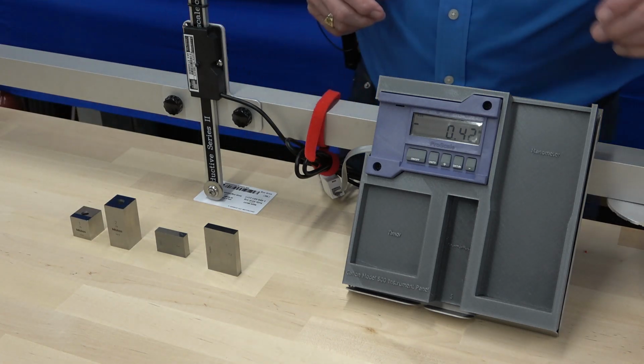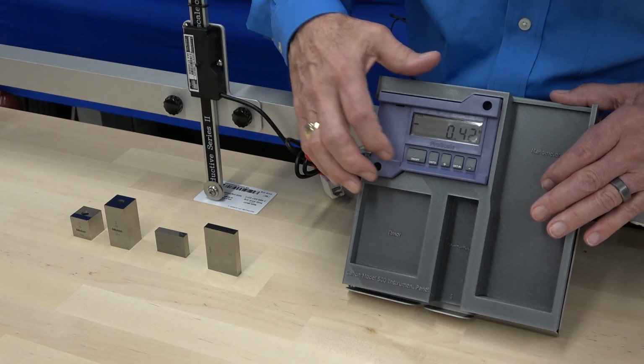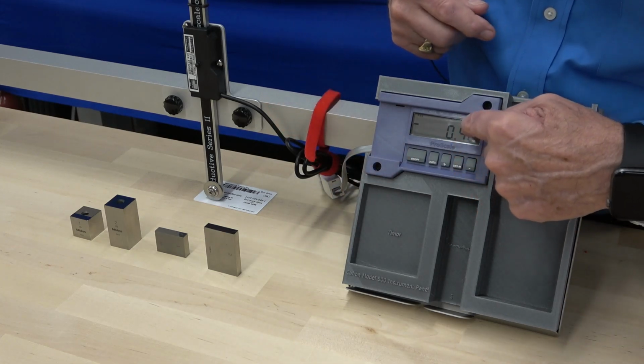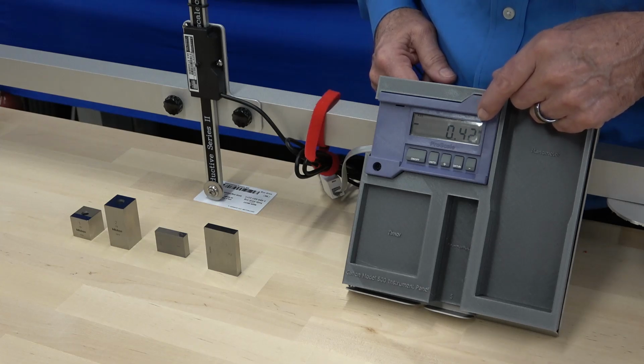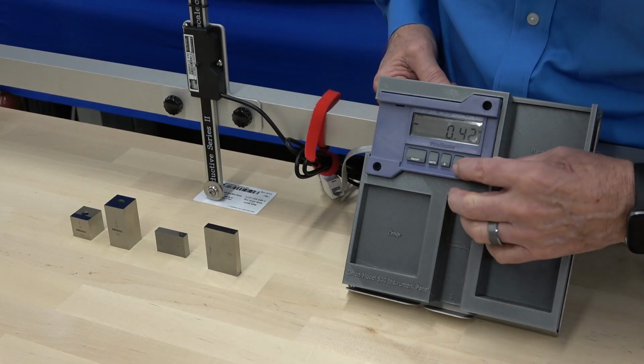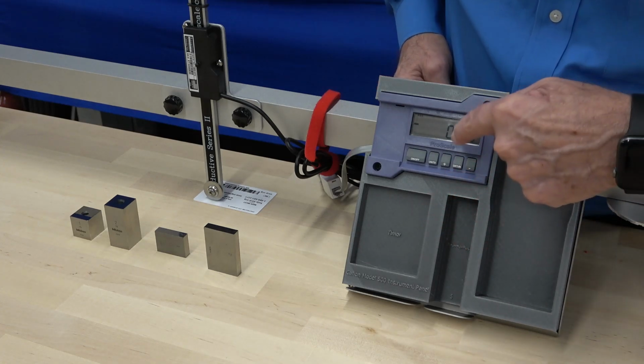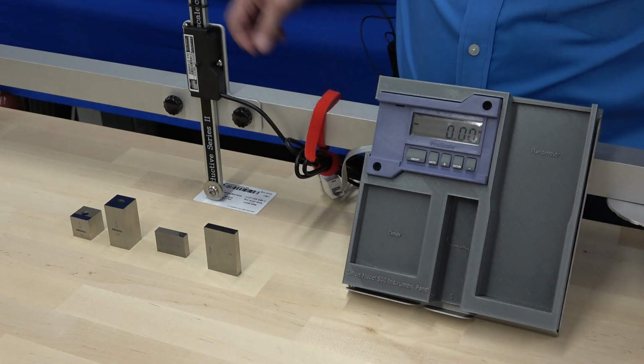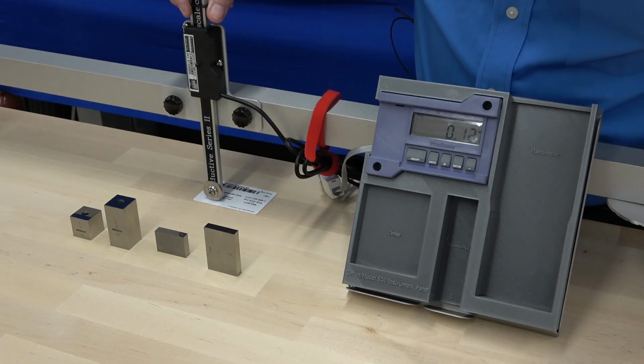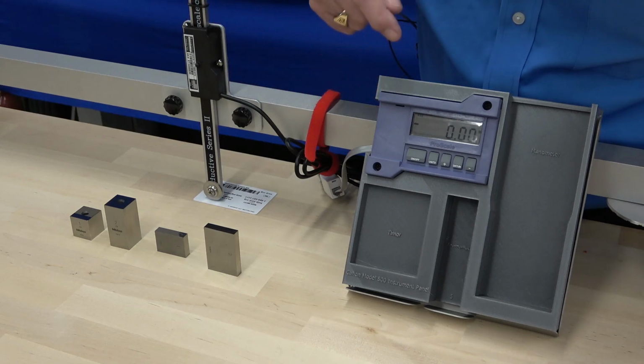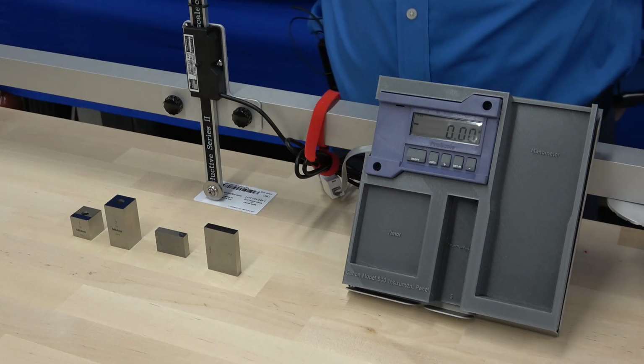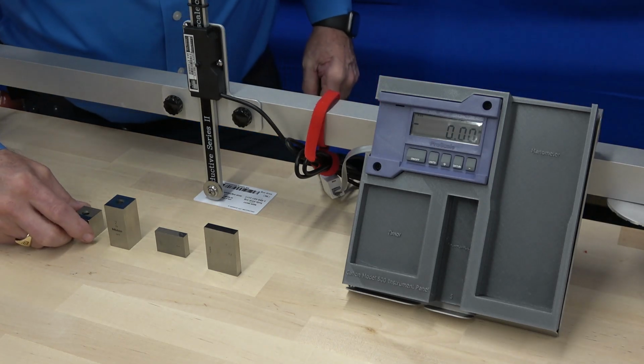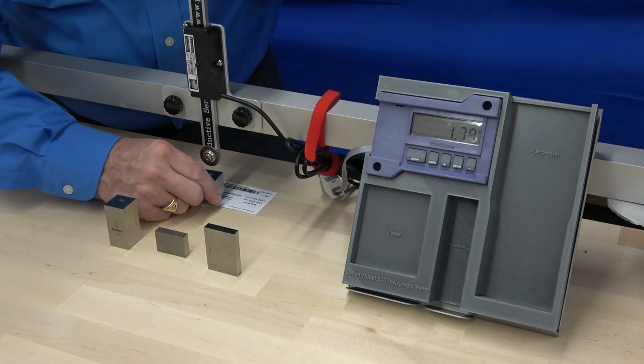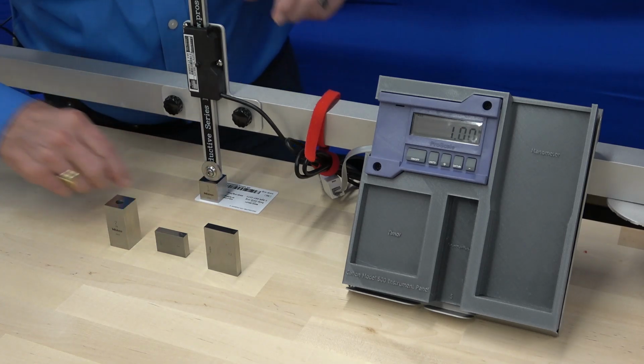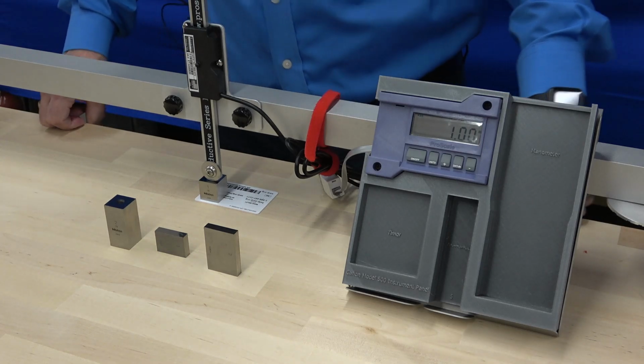So what we're going to do first is to turn on the device, and then if it's not calibrated, as you can see now it's showing 0.42 inches, we're going to hit the datum button and it's going to go to 0.00 inches. Now if we raise the device, it's going to raise it back. And I like to raise this a couple of times and make sure when I come back it's still at 0.00.